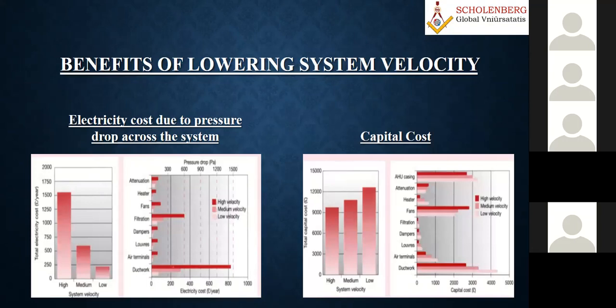Pressure drop. Normally, we always talk about high velocity, medium velocity, and low velocity design. So how much will the pressure drop be? Why should you go for a high velocity? Why should we not go for a low velocity? Because if you look at the capital cost, generally we see that if I design for high velocity, the capital cost will be less because you need less material. But the fact is not that.